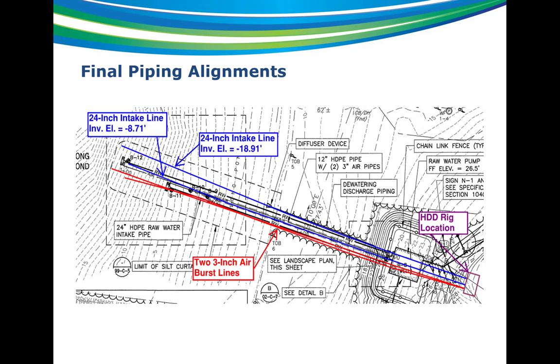This shows the final layout. You can see the two 3-inch airburst lines and then the two intakes further to the north. Elevation-wise, the deeper one was just a little more than 10 feet below, which was what we wanted. The top one lined up well with the minus 8.71 elevation we were looking for — this is the invert of the pipe, so there's an elbow that went up to the top of the screen.